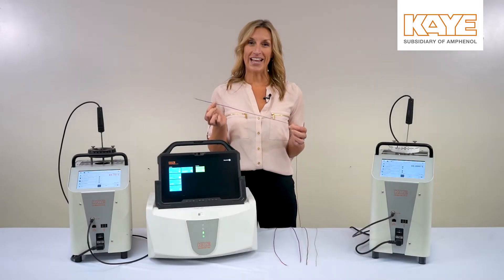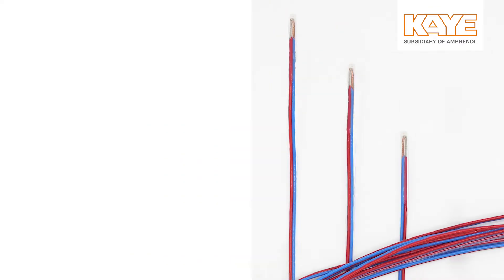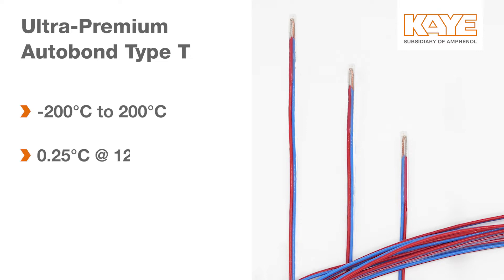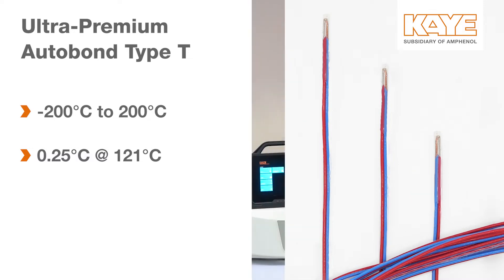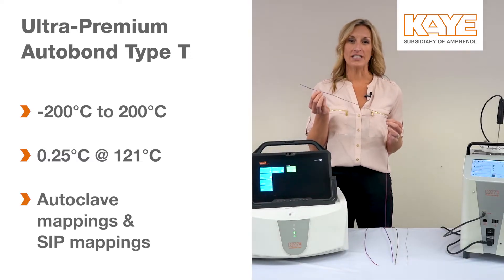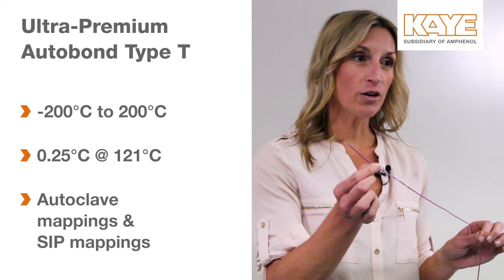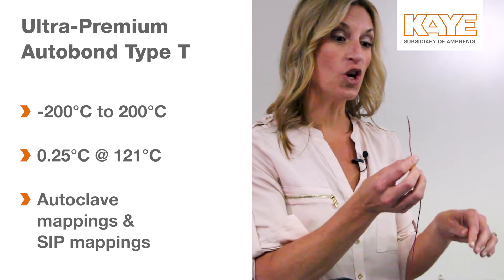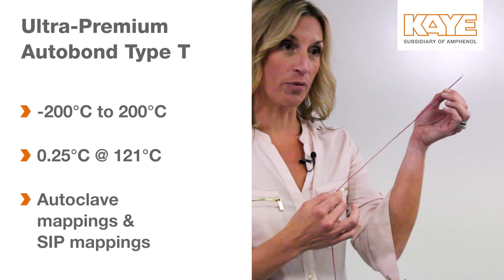The first thermocouple I'd like to highlight is our Autobond leakage-free wire. This is an ultra premium Type T Autobond wire, which gives you a range of negative 200 degrees Celsius to plus 200 degrees Celsius, and has an accuracy of plus or minus 0.25 at 121 degrees Celsius. This wire is specifically designed for autoclave mappings or steam-in-place mappings because we've removed the outer sheathing of the wire, so there's no need for a drip cut and there's nowhere for water to seep back up through the thermocouple.